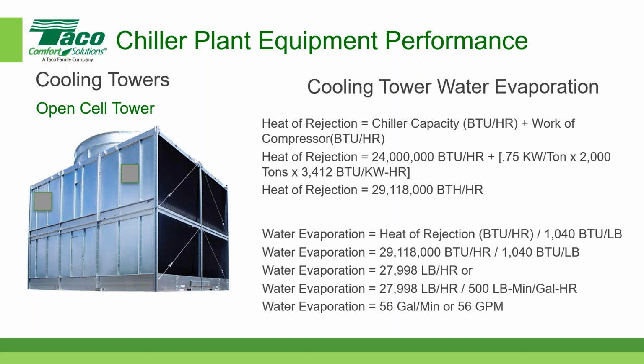The evaporation for our system, we said, was about 2,000 tons. And that means that we need about, for the evaporation, about 56 gallons per minute, roughly, of evaporating water. But that's not the only water that the cooling tower is going to consume.